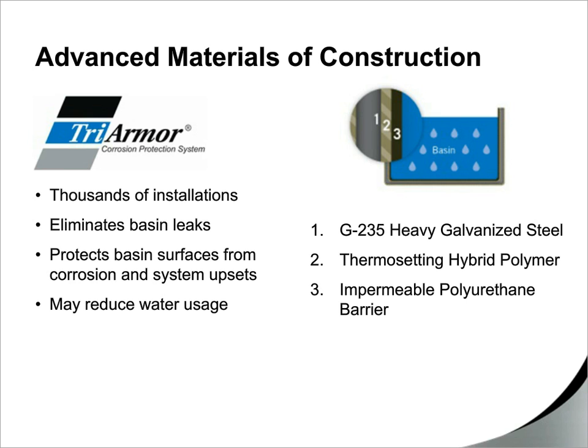It's a thick coating that's basically sprayed at the factory on top of G235 galvanized steel that's coated with the thermosetting hybrid polymer coating. And this thick coating fully adheres to the basin and completely eliminates the potential for leaks. And since it's impervious to chlorides, it really makes for an excellent alternative to 316 stainless steel.